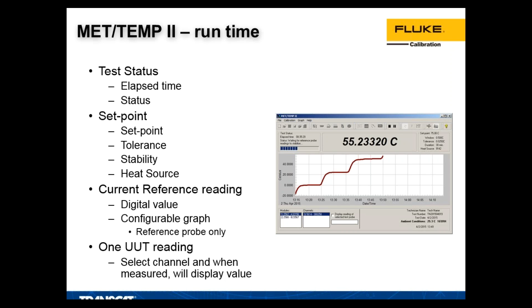The runtime in MET/TEMP II keeps track of the elapsed time — you can see how long the test has been running and which set points you're on. It keeps track of the tolerances, how close you are to the set point, and what the stability is. It indicates which temperature source is being used at the moment, and you can keep track of your reference readings and the output from the unit under test. All of that is displayed on the computer screen if you want to monitor it there.